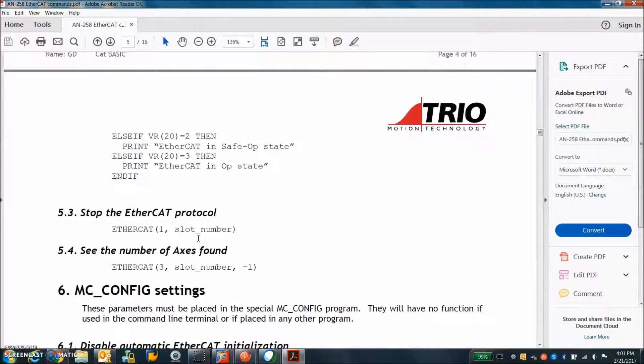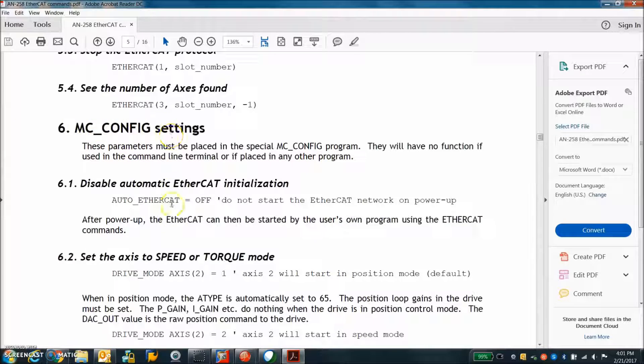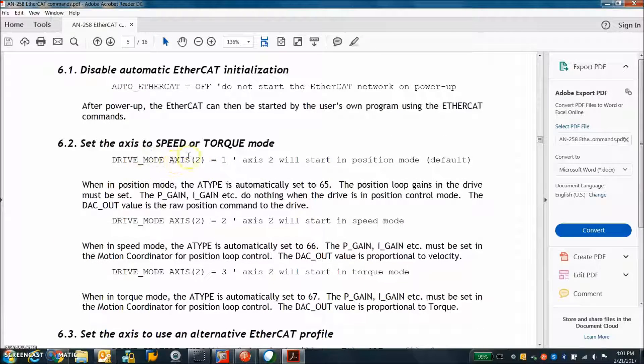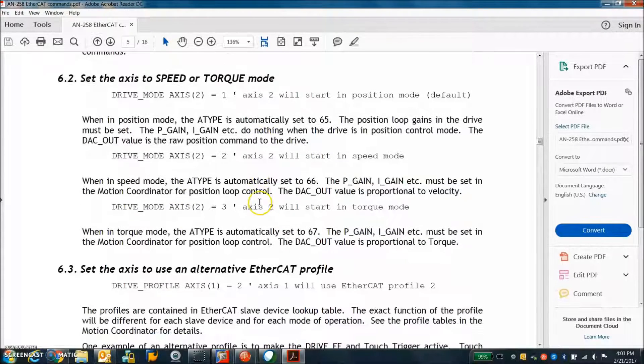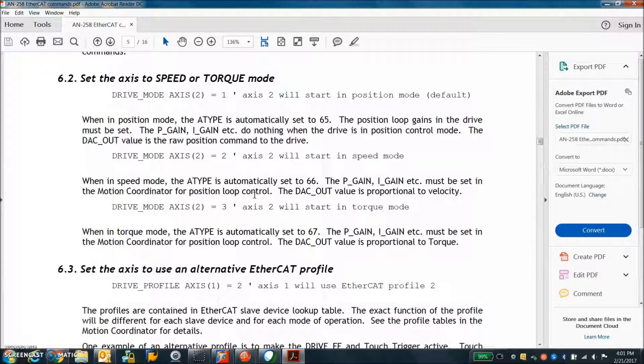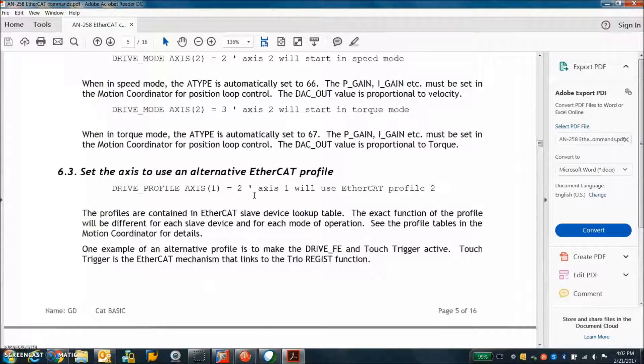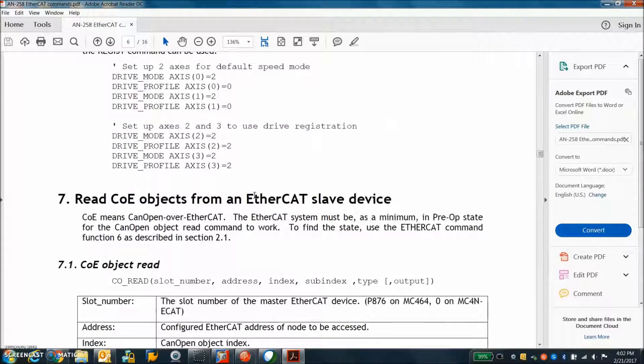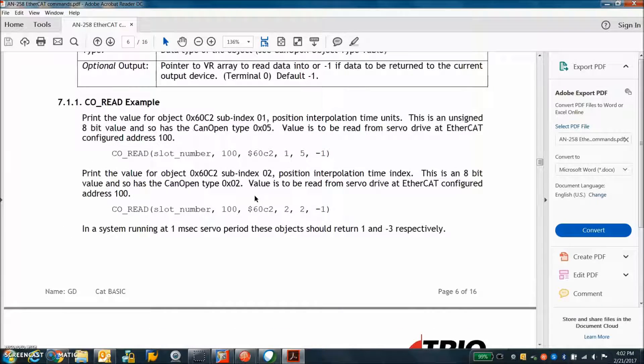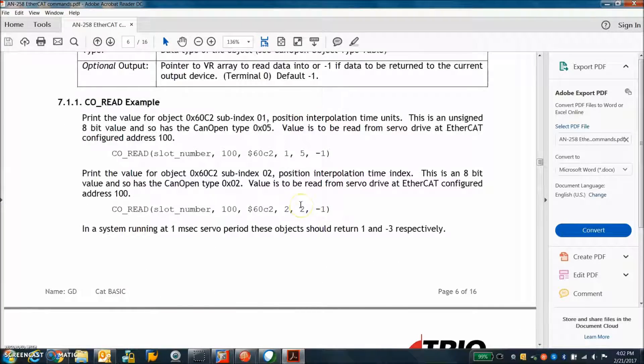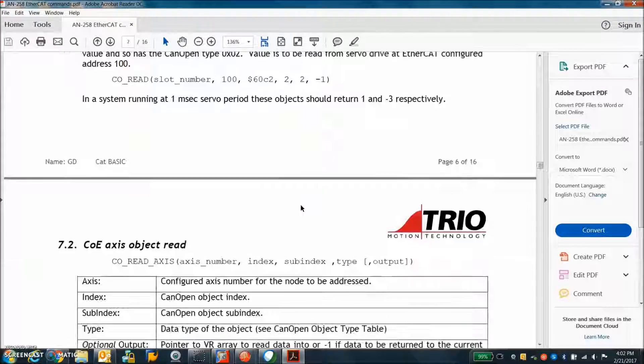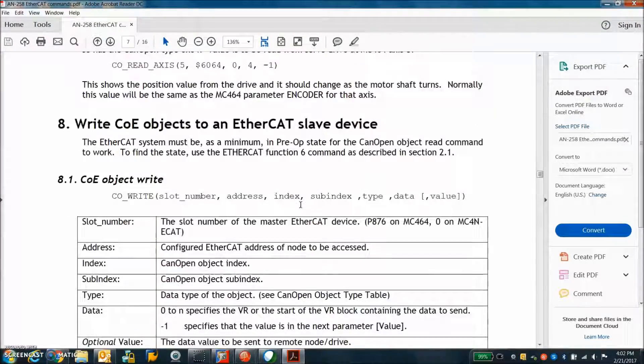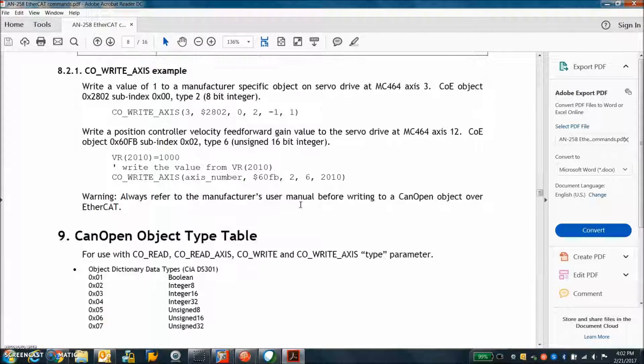And we can, here's the MC_CONFIG. This would be a program that runs after power up or reset on the controller. And again we can specify modes of operation for the drive. Normally it's a position mode doing cyclic synchronous positions. With a stepper it's open loop but with a servo you could do like a torque mode or something, but let's let's keep it simple. We can read any object in the object dictionary, so that's kind of handy, uses an SDO to read any object. You can write to other objects too, that's very very powerful.